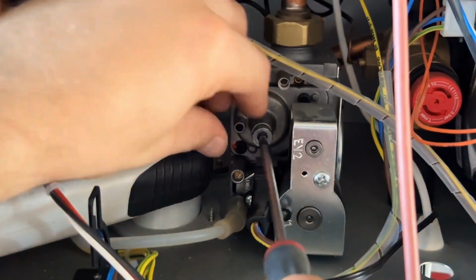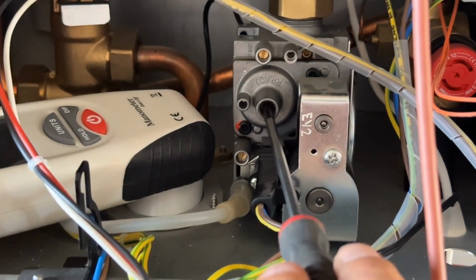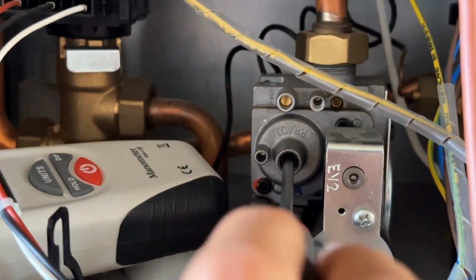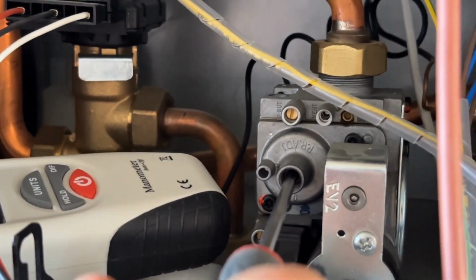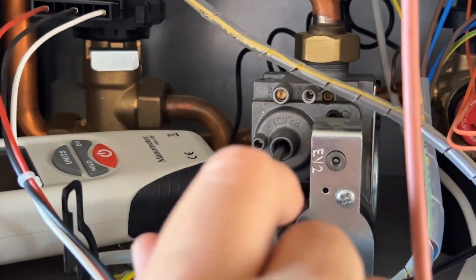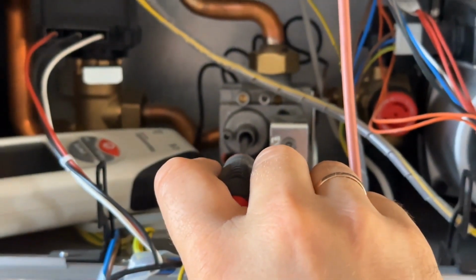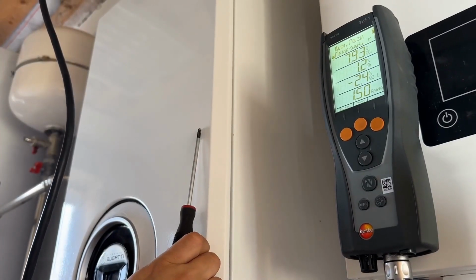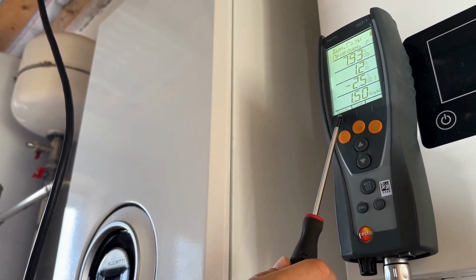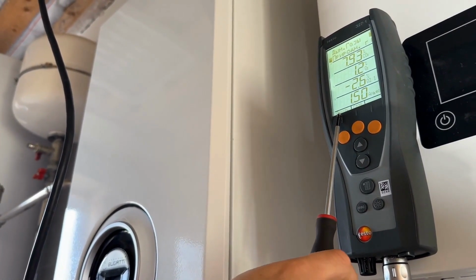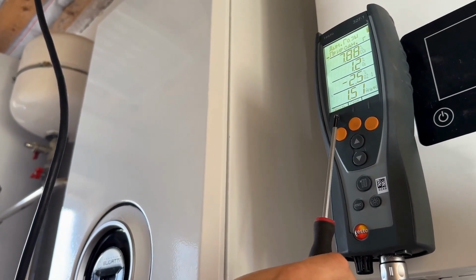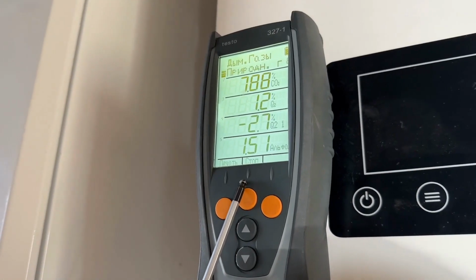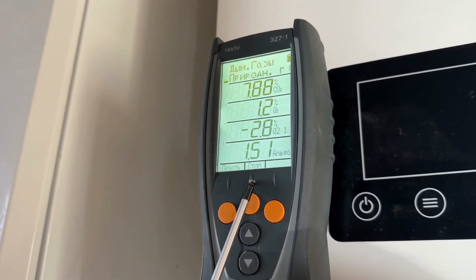By unscrewing the plug, we gain access to the adjustment screw for minimum power. By turning clockwise, we increase the CO2 value, and by turning counterclockwise, we decrease the value. After ensuring the lid is closed, we wait for the readings on the gas analyzer. It is necessary to wait at least 60 seconds for accurate results. If the results are satisfactory, we move on to adjusting the maximum power.